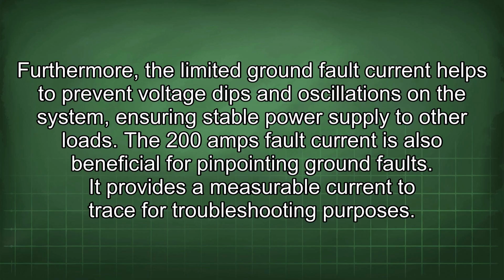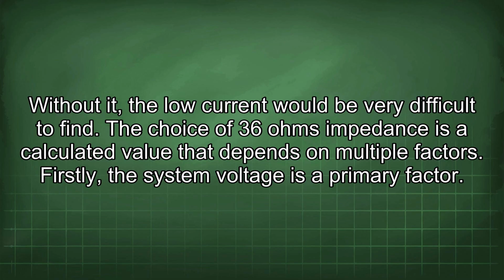The 200 amps fault current is also beneficial for pinpointing ground faults. It provides a measurable current to trace for troubleshooting purposes. Without it, the low current would be very difficult to find. The choice of 36 ohms impedance is a calculated value that depends on multiple factors. Firstly, the system voltage is a primary factor.